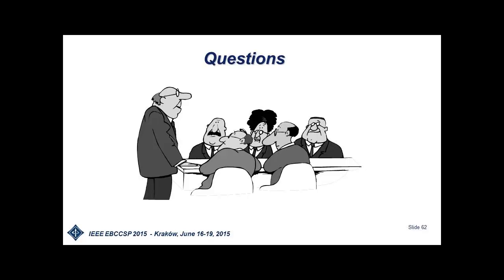Yeah, actually, it's a little bit deceptive here. I presented it in the context of wireless, but PIDPlus can be used with any analytical measurement, like a gas chromatograph. Just anything that's not updating continuously, where you only get aperiodic updates. There are a lot of spectral analyzers and gas chromatographs where you just don't get a continuous indication of what you're interested in. But PIDPlus is really a nice way to handle that. Before that, people took the PID and did a bunch of ad hoc stuff to it, right? Turn on the reset for 10 seconds, turn it back off when you get a new measurement or something. It was all because you didn't have a good way to handle the reset. Well, with PIDPlus, you can use it for that.